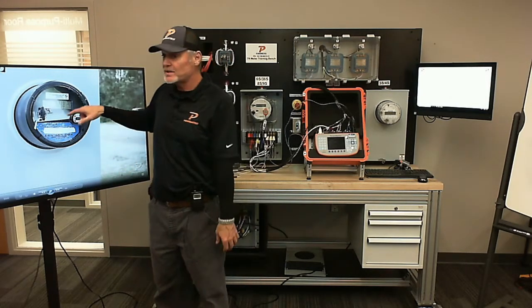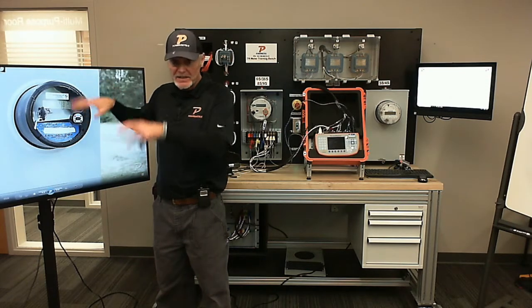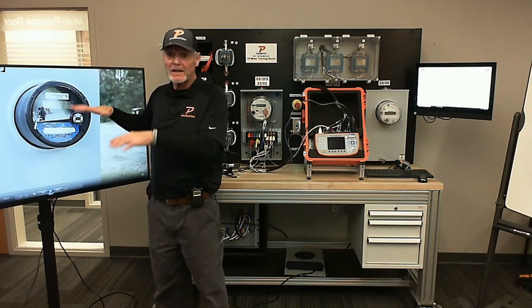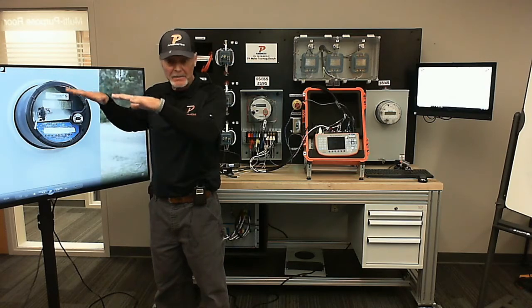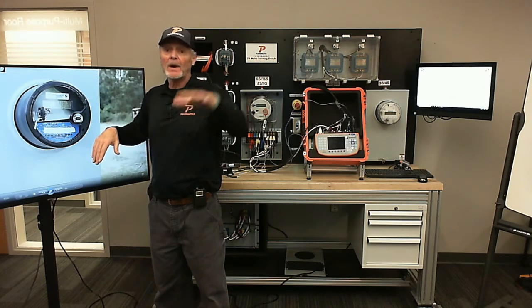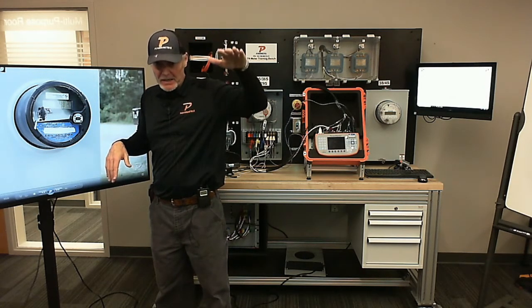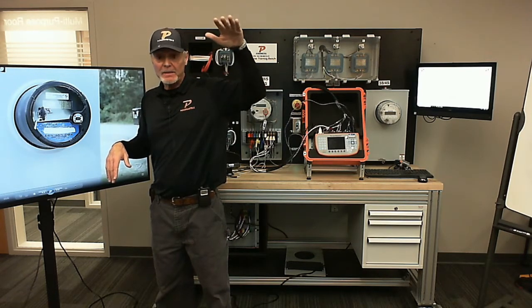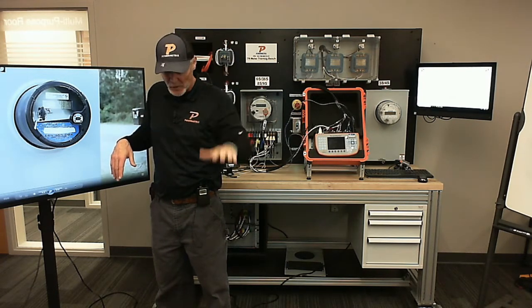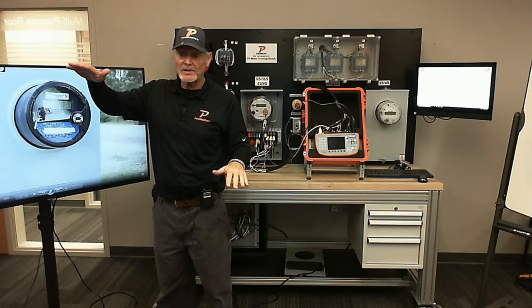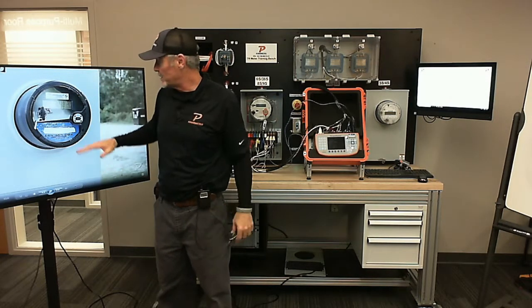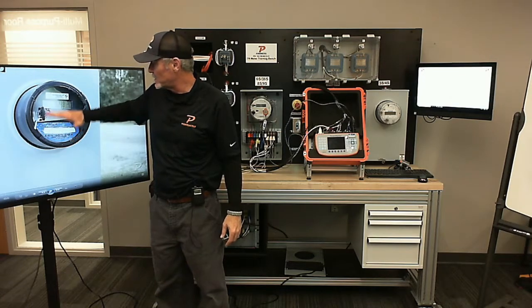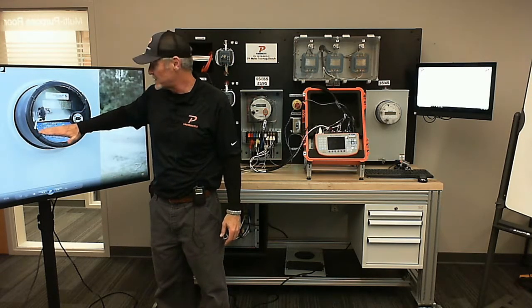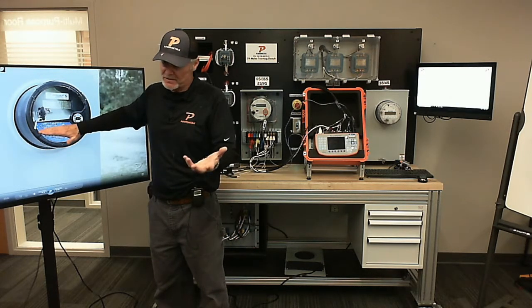But this is a class 20 meter. That's why you have the test switches, the CTs and everything to bring it down. We always say they're step down transformers for a VT, or voltage transformer, or a PT, potential transformer. It brings the voltage down. Then our CTs, or current transformers, bring the current down, because this is a class 20 meter, so it's made to work with 20 amps, okay, max. Otherwise, if you get over that, it's not good.